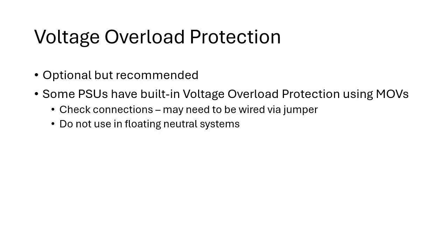So what some power supplies have is built-in voltage overload protection using an MOV type device. It may be that's not wired in as standard. You may need to connect that via a jumper. It may be something that's not supported in floating neutral systems, so again, check for vendor documentation. But the idea of that voltage overload protection is if the voltage goes higher than the maximum specified, so for example for a PLC that might be 30 volts, what the MOV does is effectively turn off the output, so that's often called crowbar protection. It can either turn off the output just by going open circuit, or some devices go short circuit, and that would trip a fuse or MCB as well. So there's a variety of different protection options there.